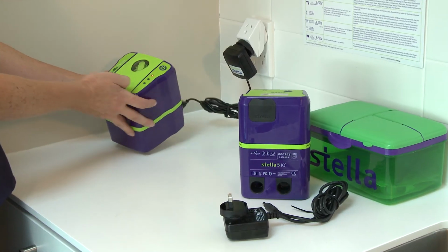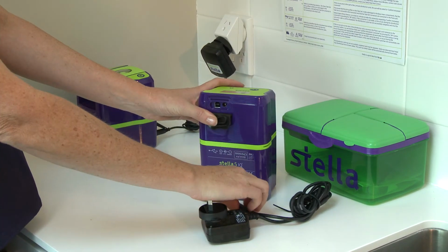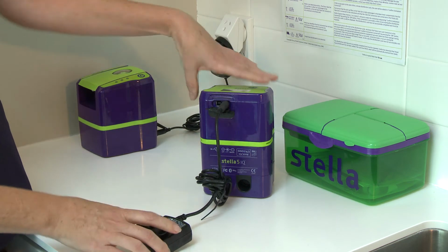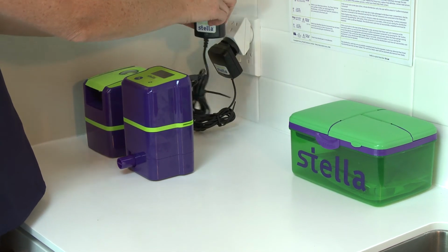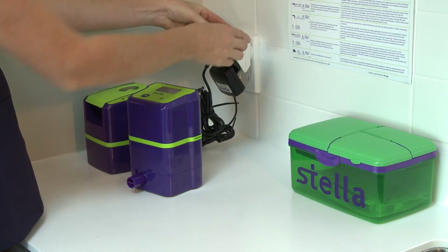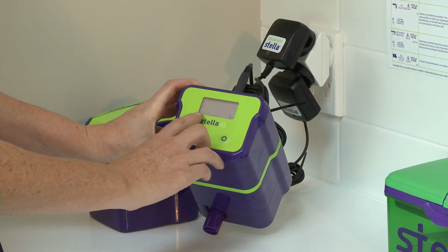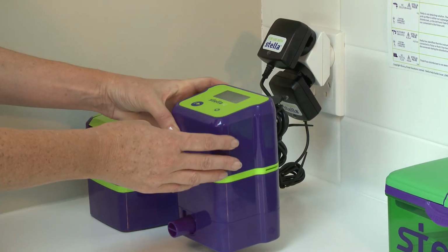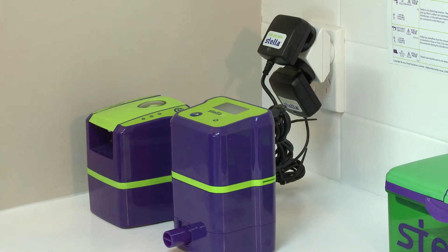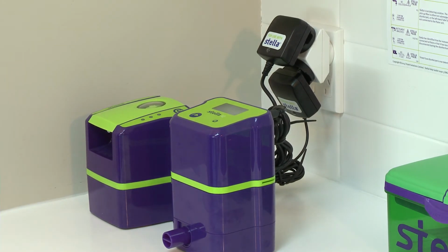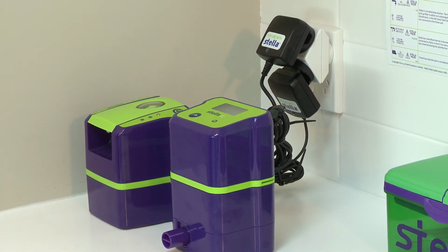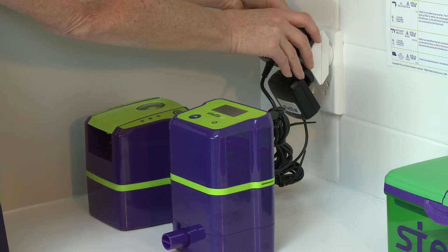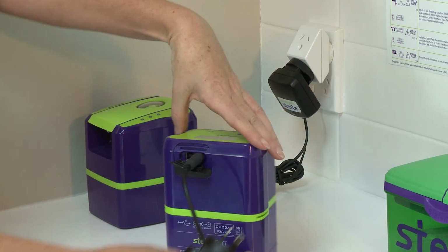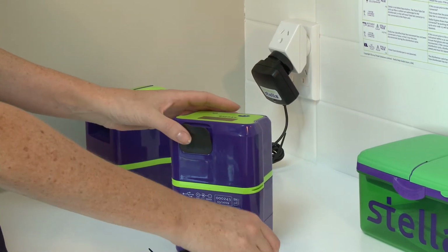When charging is completed, press the protective covers firmly into place, as ingress of fluid into this area will damage the units. Equipment must receive a full 12-hour charge at least once a month. Failure to do so will cause the battery to age, and the number of disinfection cycles the equipment can complete will decrease. If the equipment has not received a full charge for 30 days, the graphics will report a charge battery warning and shutdown, forcing the user to charge before the equipment can be used.